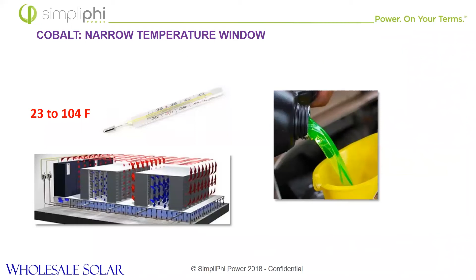So let's compare that 23 to 104 degree Fahrenheit range to what we can offer: our operating temperature is -4 degrees Fahrenheit to 140 degrees Fahrenheit, with no need for coolant or special HVAC or ventilation equipment. This should be distinguished from charging temperature—you don't want to charge the batteries below freezing or above 120 degrees Fahrenheit.